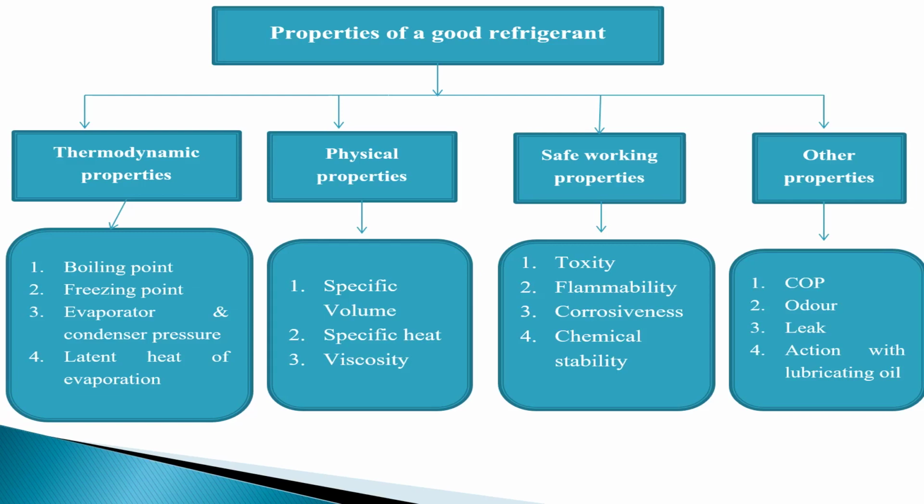Whenever we are using a refrigerant in a circuit, inside that it should not freeze. So the freezing point, the temperature at which it solidifies, should be very, very low. So inside the circuit, it should not solidify. Then the evaporator and condenser pressure, the pressure which is operated in the evaporator and the condenser, they are very important. So they should possess proper evaporator and condenser pressure working conditions.